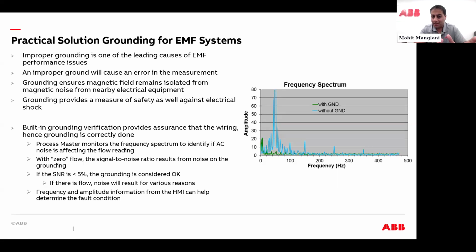Improper grounding or cross-bonding is by far one of the leading causes of mag meter degradation or performance. It will cause you to have issues in your accuracy. As I mentioned, this is a 0.2% device. On top of that, when you're doing control, obviously you want a stable output signal. So again, bonding and cross bonding helps maintain that stable signal. You want to make sure it's isolated from other heavier electrical equipment. And grounding is just good practice in general for any large electrical devices that you have.